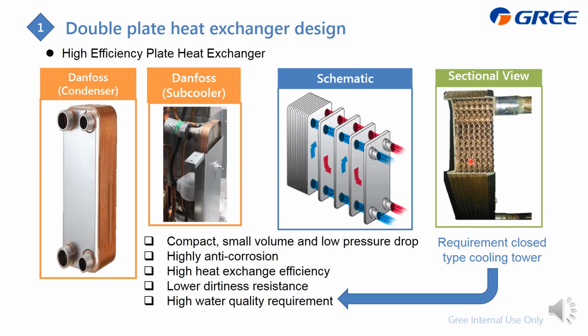The different flows just make heat exchange inside. You can also find that the flow itself is made very turbulent, which also makes the heat exchange very turbulent and can raise the heat transfer efficiency. Also, as the gaps are very tiny, we require higher water quality. This is why we require the cooling tower to be closed.